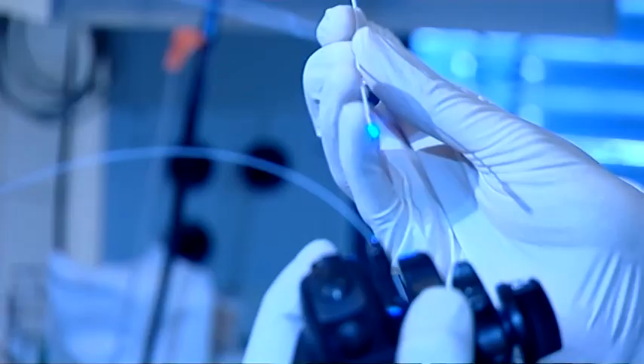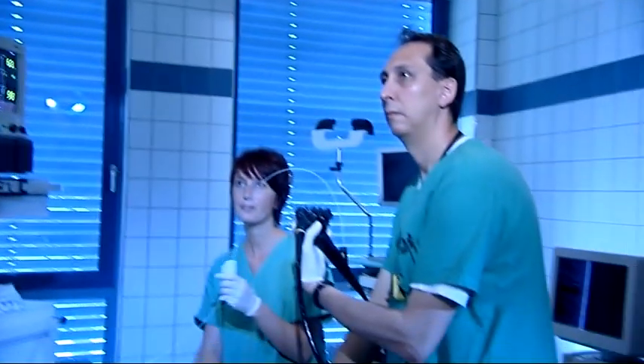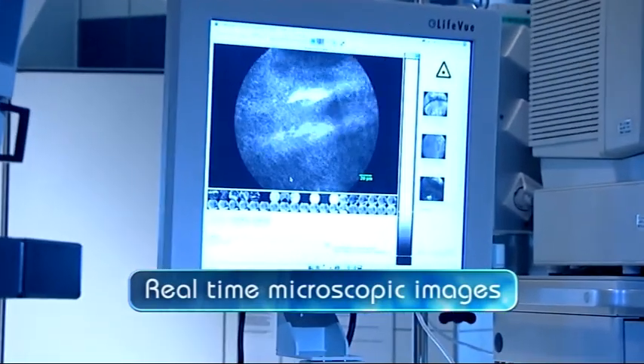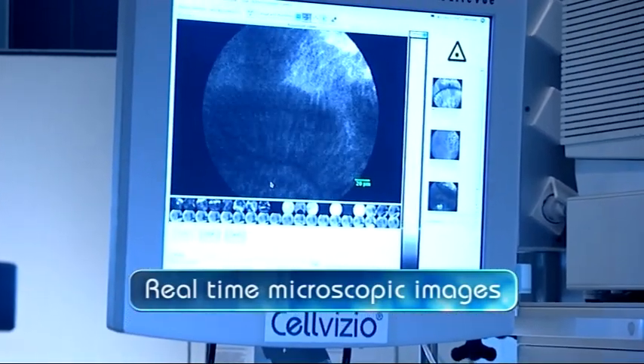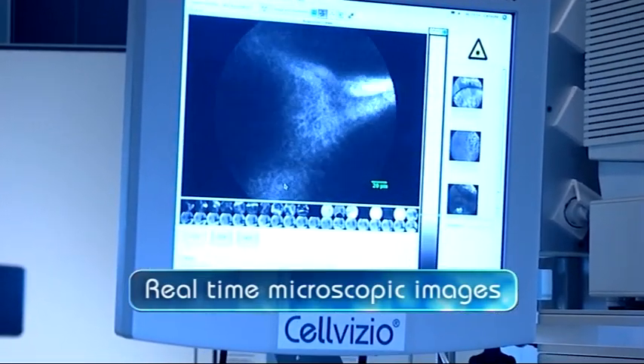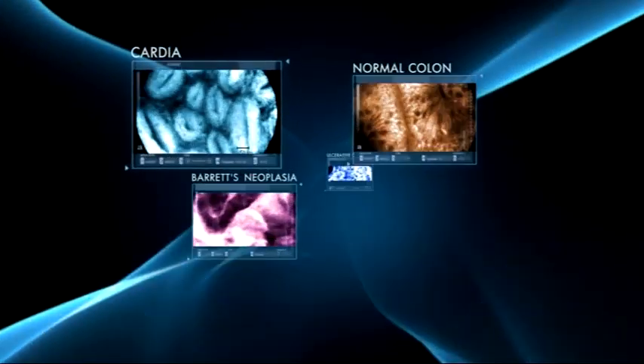How does the Cellvizio system work? The physician performs an endoscopy, and when he encounters a suspicious area, he inserts the confocal mini probe into the operating channel of the endoscope. Simple contact between the tip of the mini probe and the mucosa generates real-time microscopic video images, viewed directly on screen and recordable.